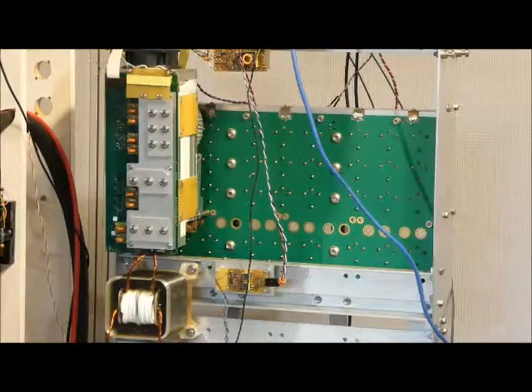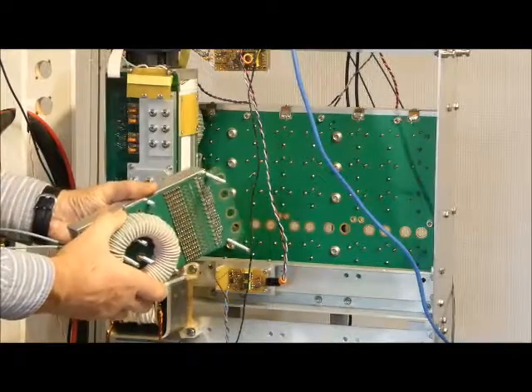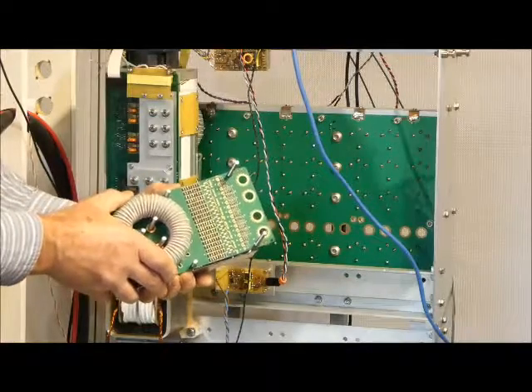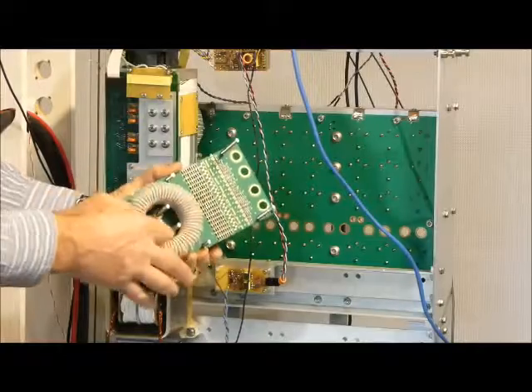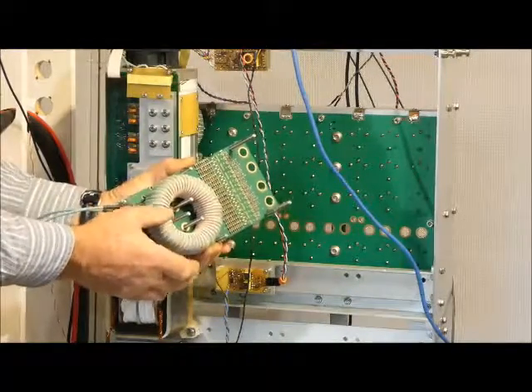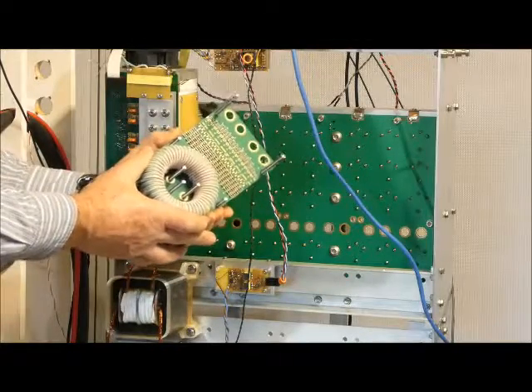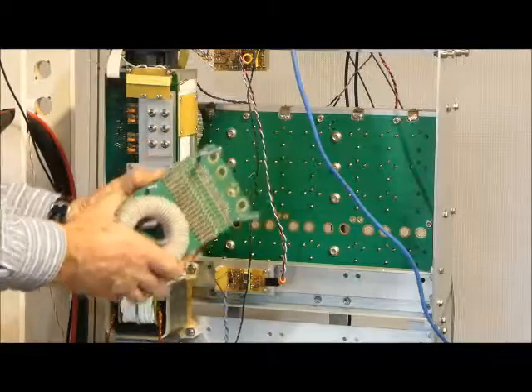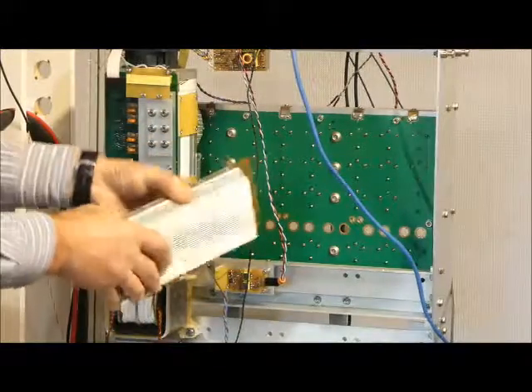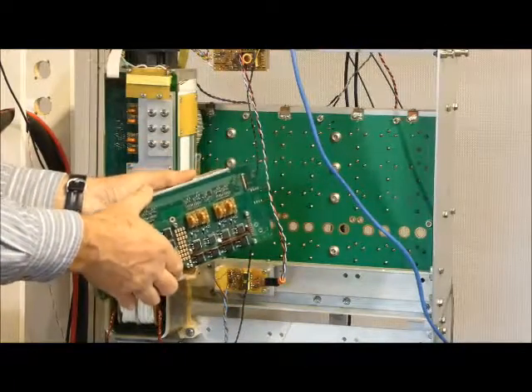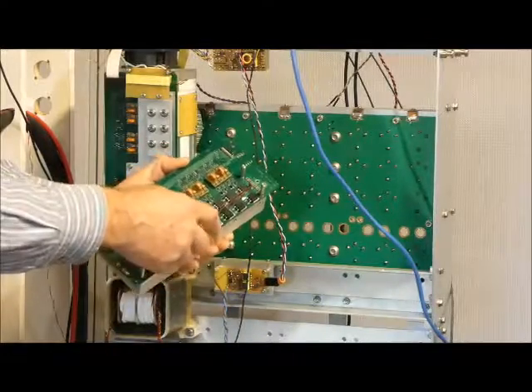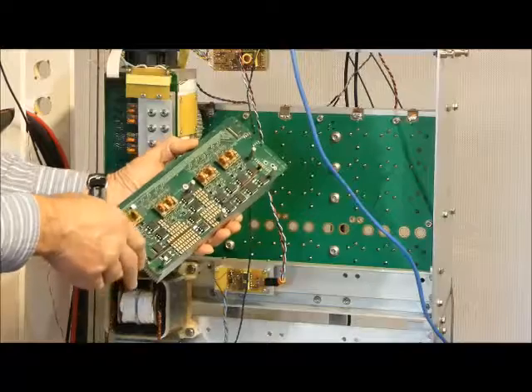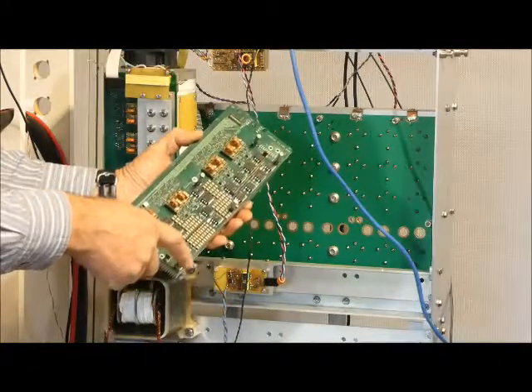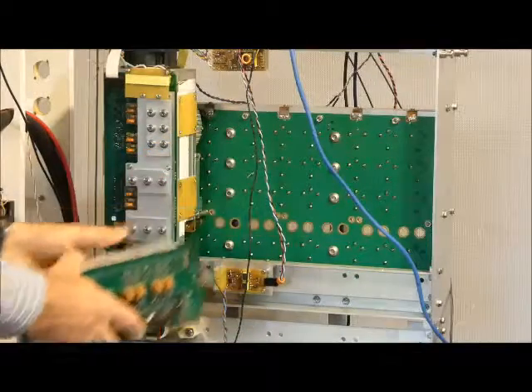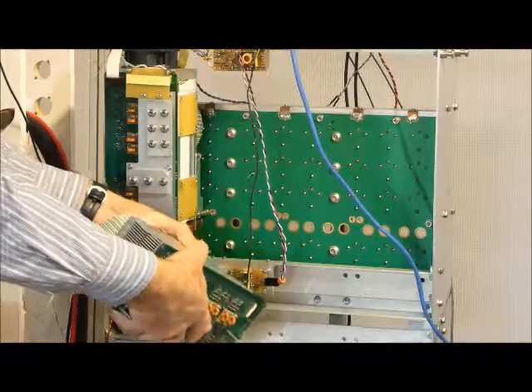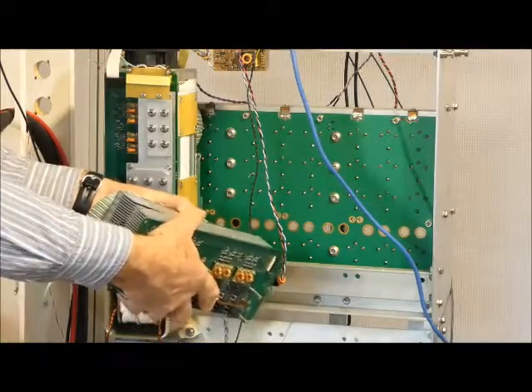The actual power module looks like this. This is the low voltage board, all surface mount components, so it's very easy to manufacture and very small. There is a transformer here which steps up from the 24 volts to 500 volts. That is quite small, and it can easily handle 5 kilowatts. This is the high voltage board, again all done with surface mount and mounted on its own heatsink. In this section here we have a rectifier which turns the output of the transformer into the 500 volt DC, and in this section the pulse width modulation. These two boards mount with the heat sinks tip to tip to make a nice channel to blow air down for cooling.